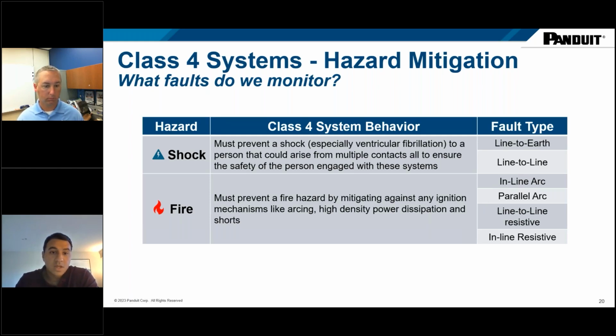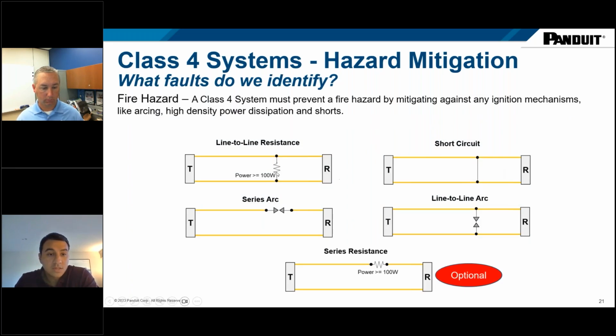If we take a look schematically at what those look like, think of T as the transmitter and R as your receiver, and this is just a schematic view of how these faults could represent themselves. So you have the line-to-line resistance fault, you have a short circuit, a series arc, a line-to-line arc, and then there's also a 5th optional one. A class 4 system does not necessarily need to adhere to this type of fault.